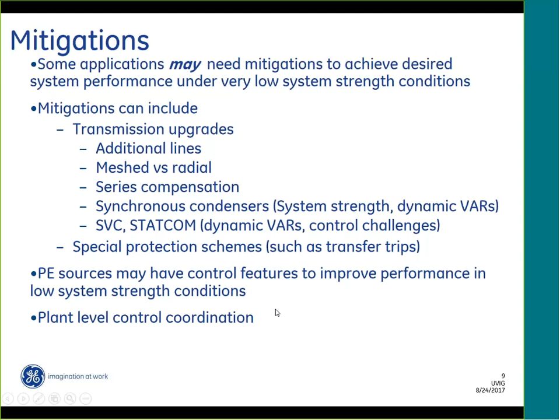Ideally, you would use the control features in the power electronic sources. In general, I would say that in the last years, we've seen significant improvements in the performance and in the availability of features of power electronic sources for low system strength. And then also power plant coordination. Some of the examples that we talked about were related to availability of reactive power after a fault is clear. It's quite usual that these low system strength conditions are met when you have a large number of wind plants next to each other, maybe 5, maybe even more. So coordinating the plant level controls of all these plants enables a better use of the available reactive power and can help mitigate some of the issues related to weak grids.